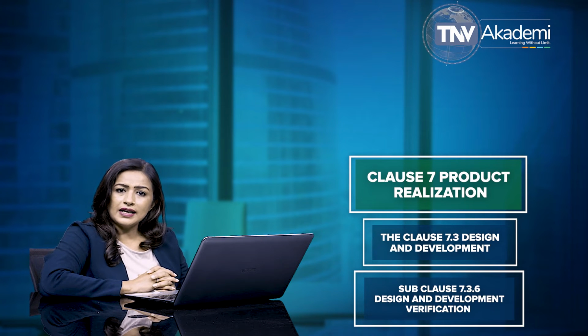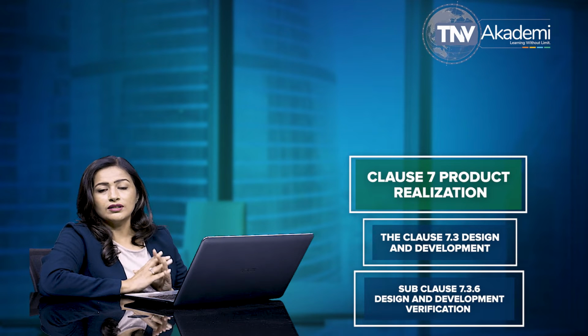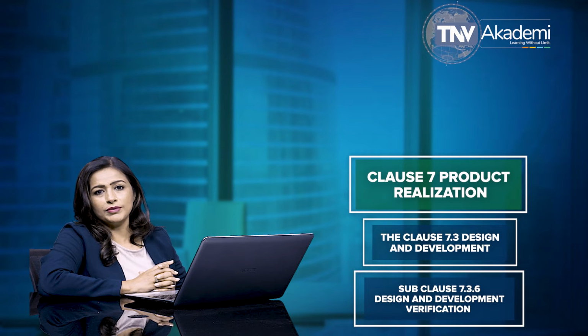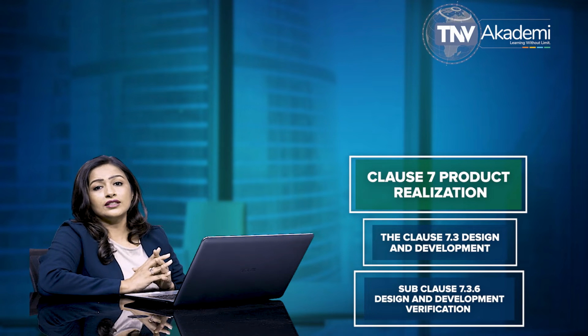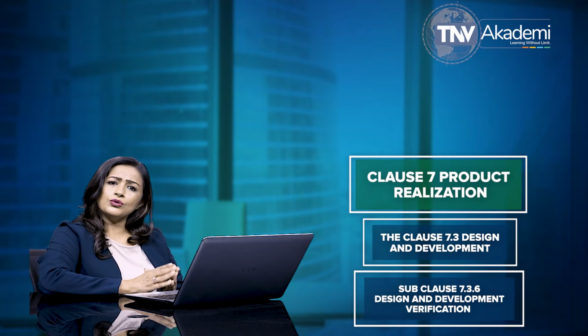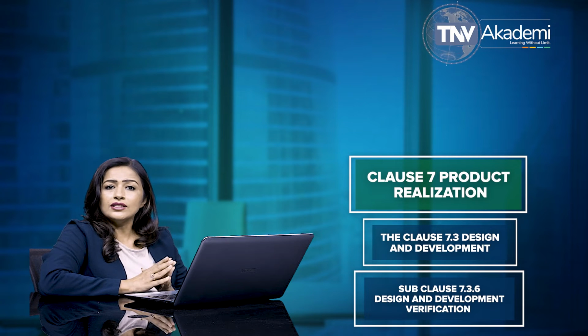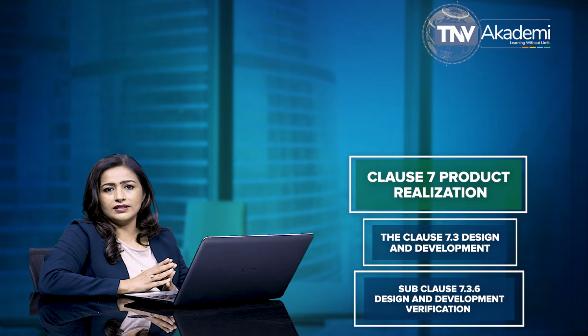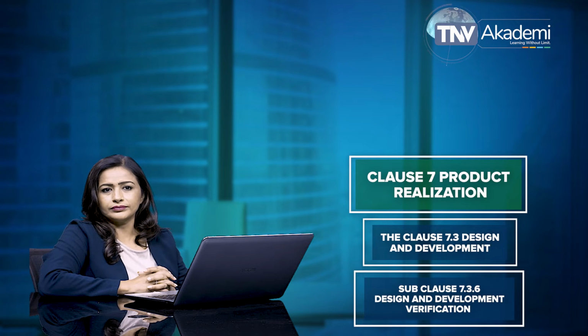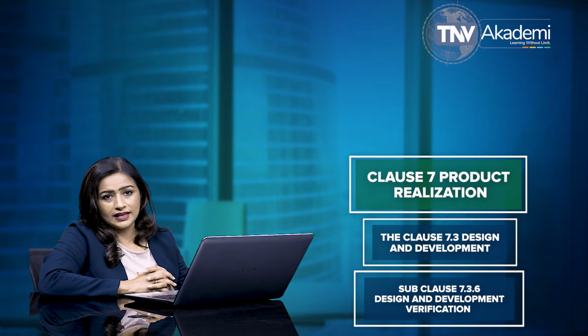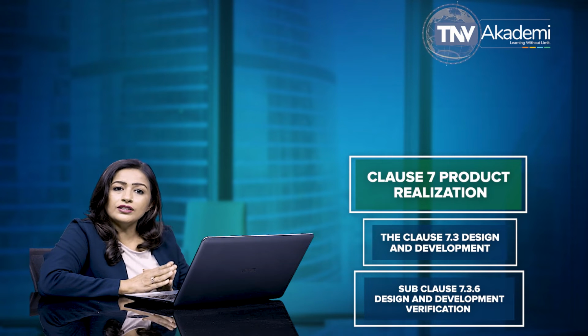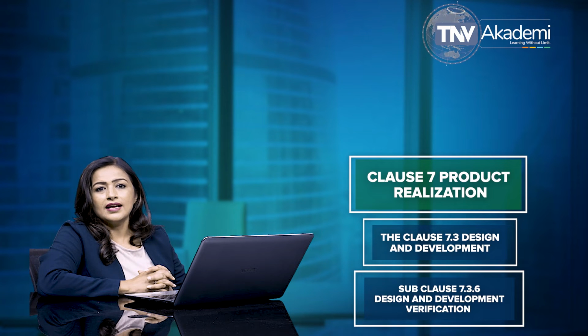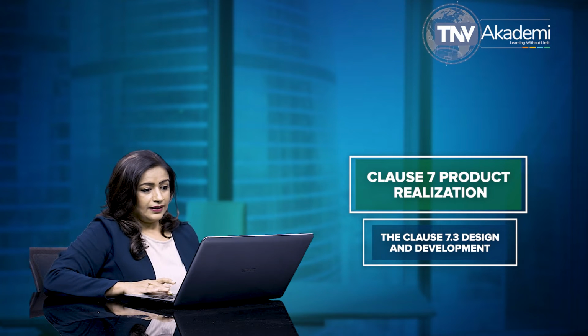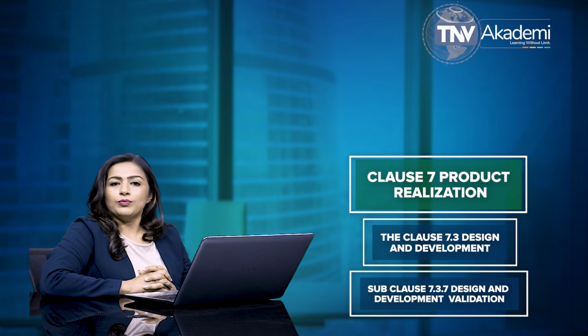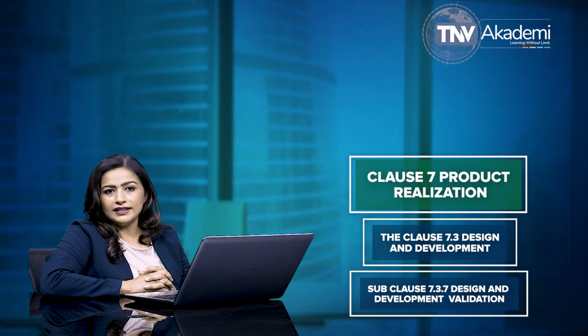The clause further specifies that verification is required to include confirmation that the design outputs meet design inputs when so connected or interfaced, if the intended use requires that the medical device be connected to other medical devices or have an interface with them. Subclause 7.3.6 says that an organization is required to maintain the records of the results and conclusions of the verification and necessary actions. Let's discuss now subclause 7.3.7, Design and Development Validation.